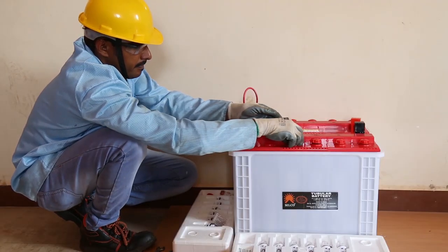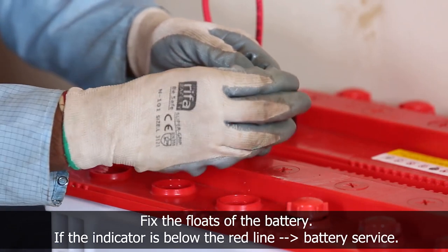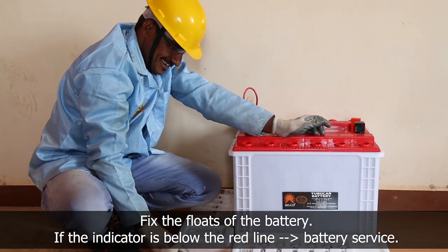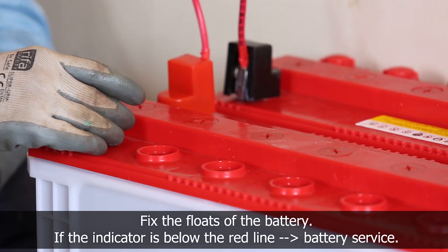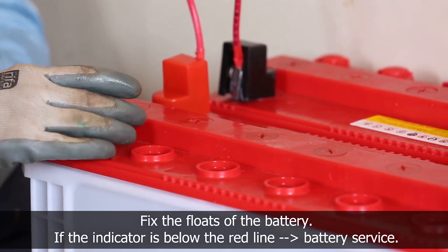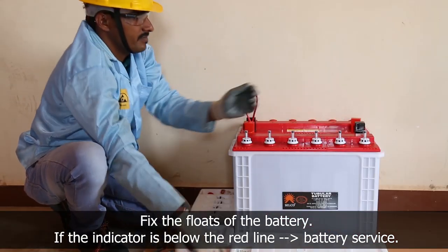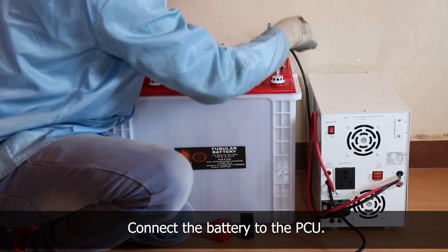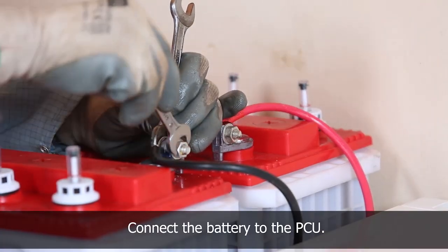Remove the battery cap and fix the floats of the battery in order to check the water level. If the indicator is below the red line, the battery needs to be serviced. Connect the battery to the power conditioning unit.